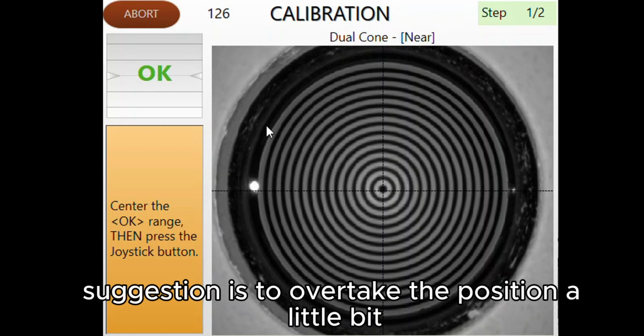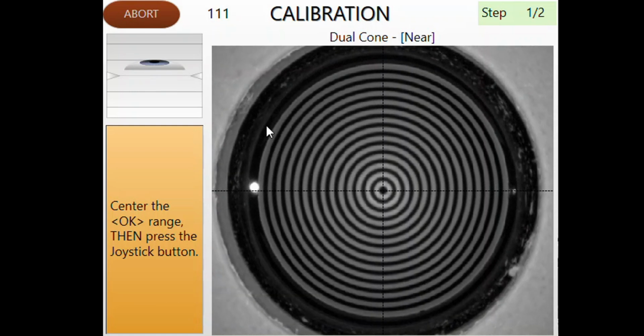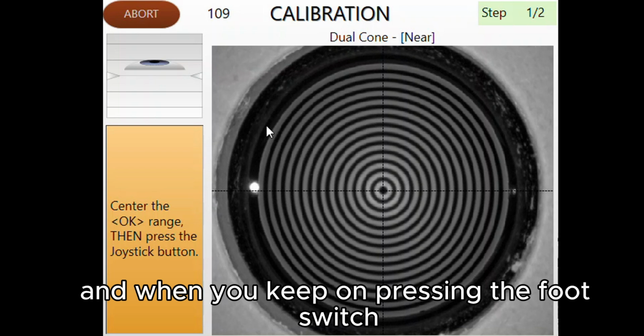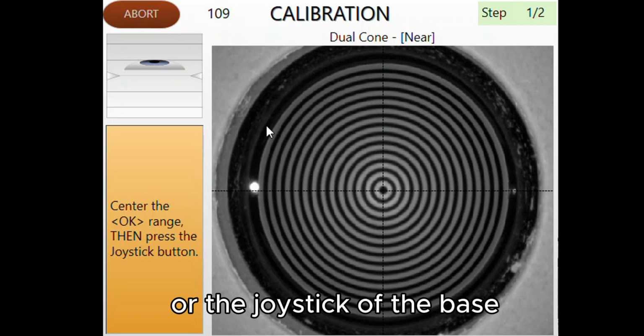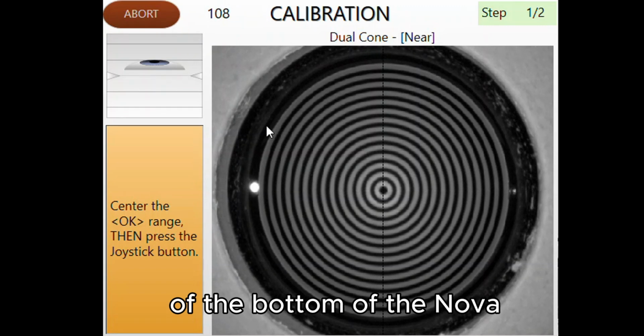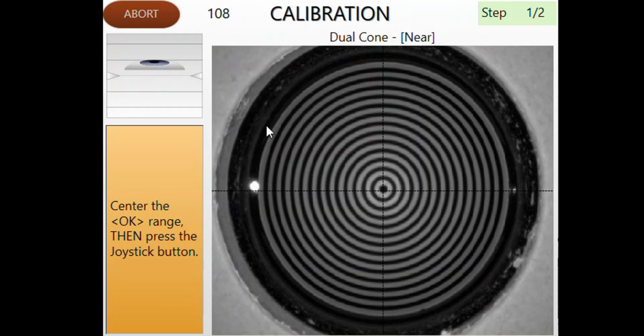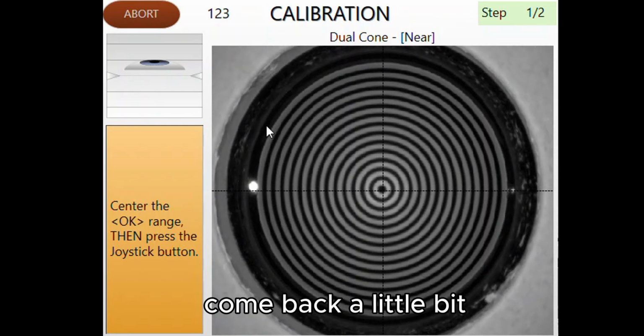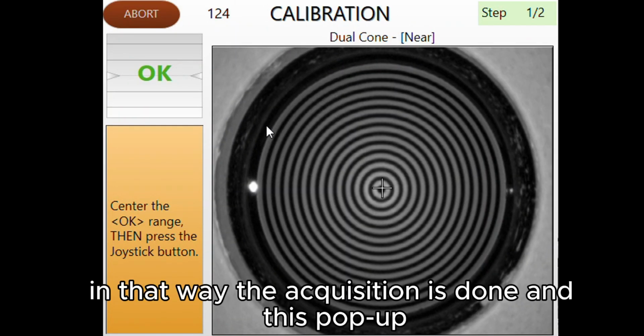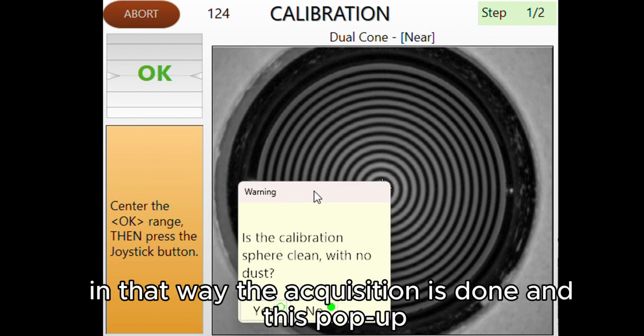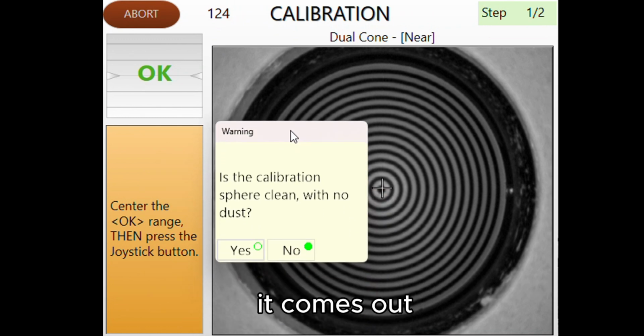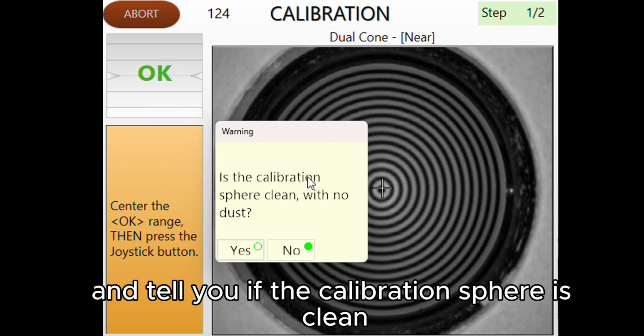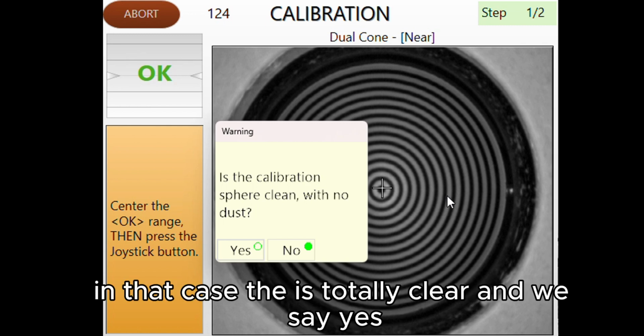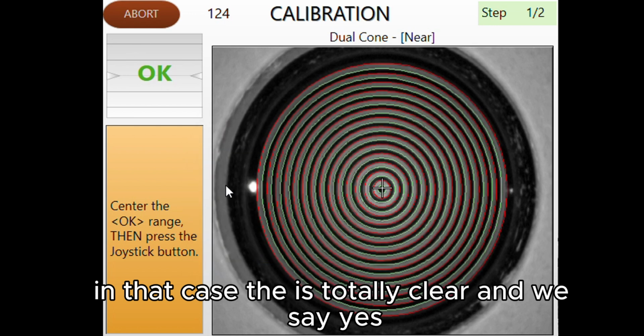A suggestion is to overtake the position a little bit, and when you keep on pressing the foot switch or the joystick of the base, or the bottom of the Nova, come back a little bit. In that way, the acquisition is done, and this pop-up comes out and tells you if the calibration sphere is clean of dust. In that case, it's totally clear, and we say yes.